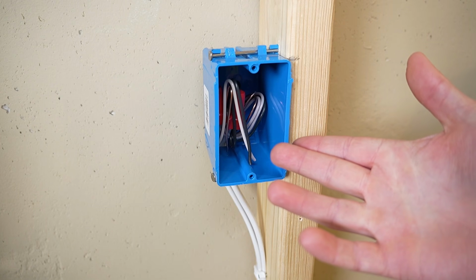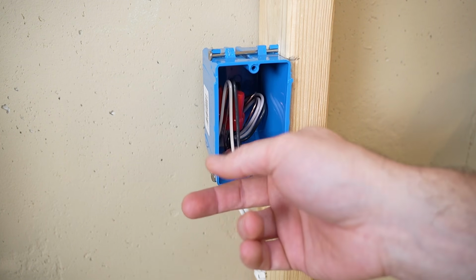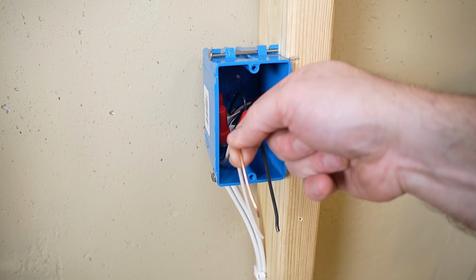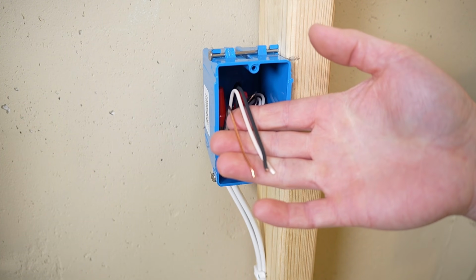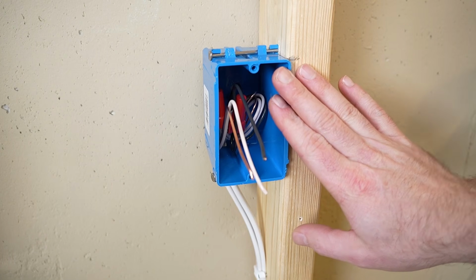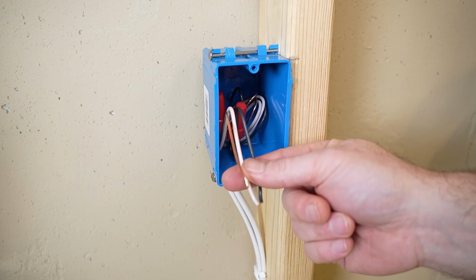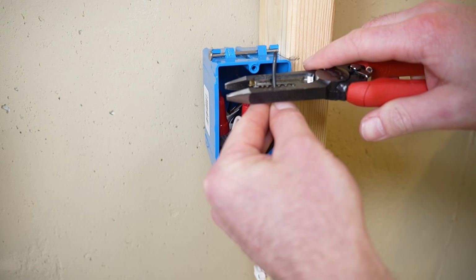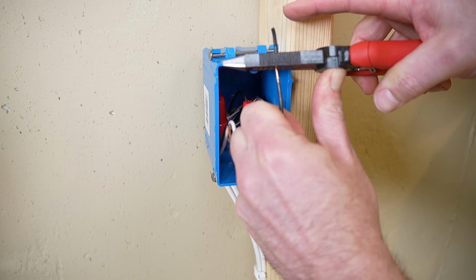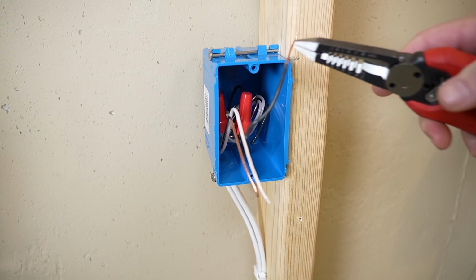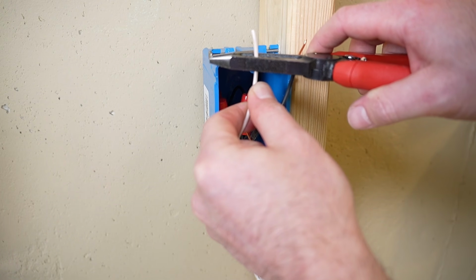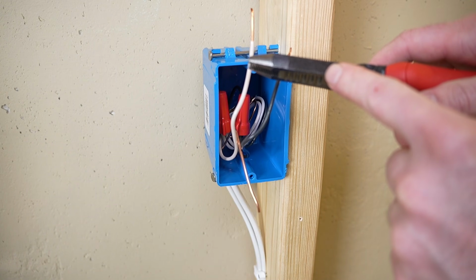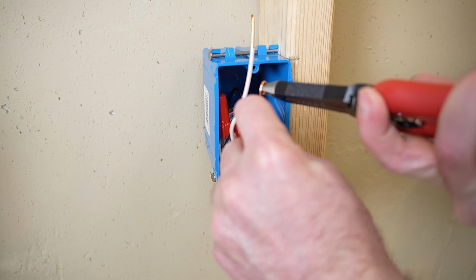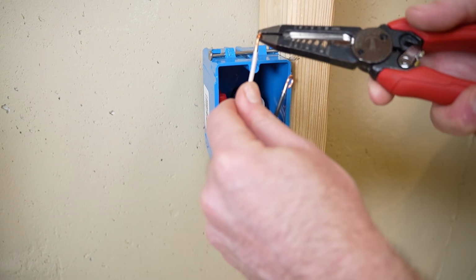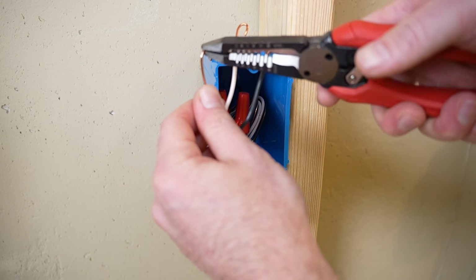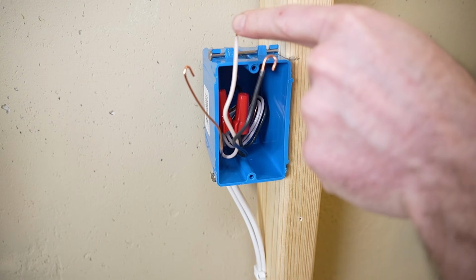So once we come back to a box after the wall has been finished, hopefully all of our wires are still intact. And we can go ahead and pull out just the 3 wires that we left there. Remember, this first box we did the pigtail method. So all we need to do is pull out the pigtails. We're gonna strip these back long enough that we're able to make a good loop. This is roughly 1 inch, and we'll strip out the neutral as well. I like using these needle nose wire strippers. Makes grabbing the tip really easy to put a loop on. And we'll put our loops on all 3 of these wires, hot, neutral, and ground.